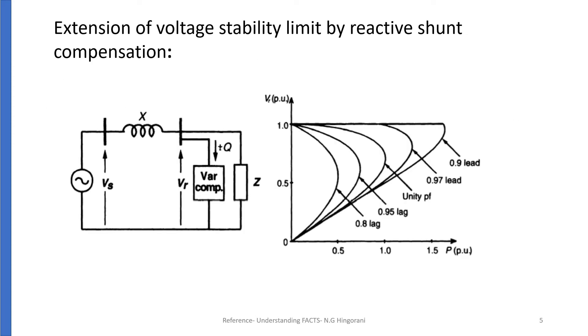Extension of voltage stability limit by reactive shunt compensation: here we can see the same radial line is being given compensation at the load end. We can see the change in the PV graph obtained due to this shunt compensation provided at the load end, and we can see that the stability margin is increased.